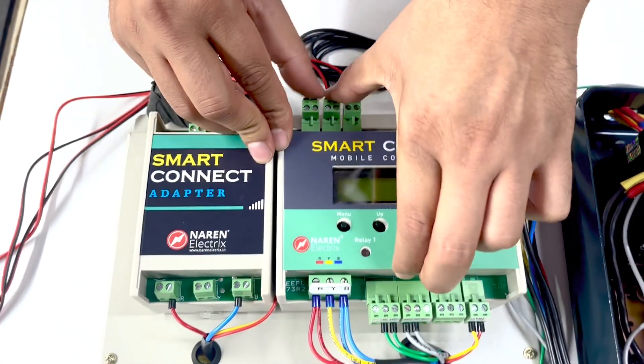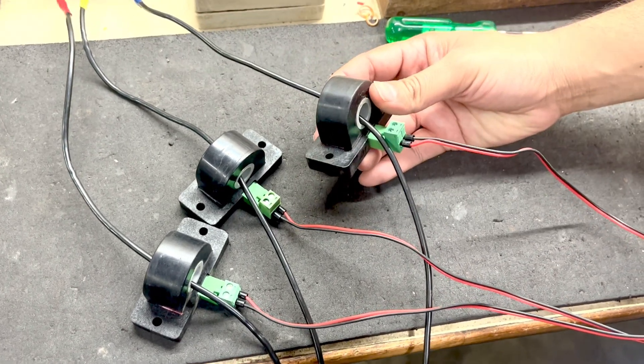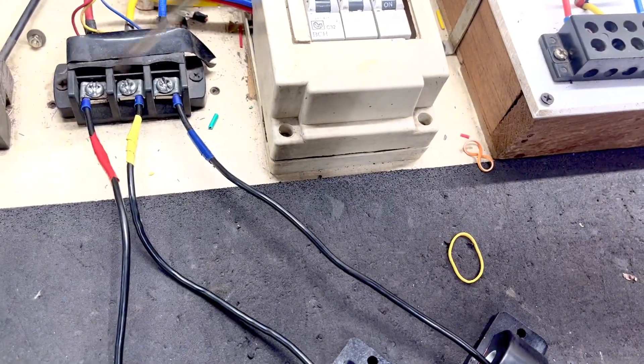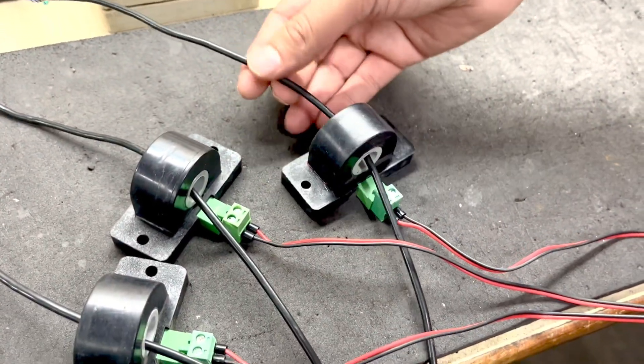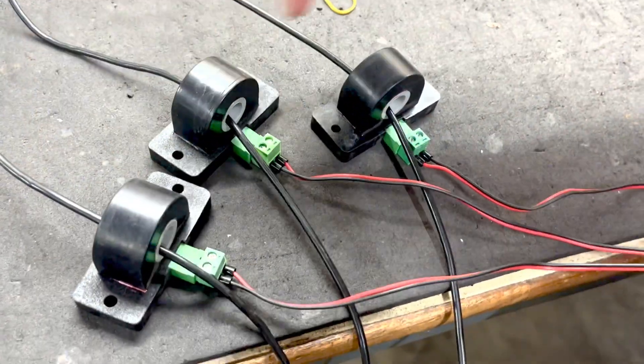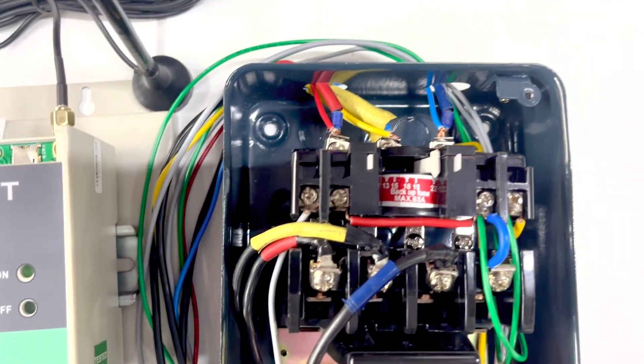The CTs have respective connectors and wires coming out the other side with connections already made. This is the incoming to the starter — you can assume this to be a fuse through which you are driving the main three-phase power supply. The three wires coming into the starter — red, yellow, blue — these three thicker wires should be passed inside the holes provided in the CTs. R for red, Y for yellow, and B for blue, so all three independent lines pass through three different CT holes and then connect to the starter.